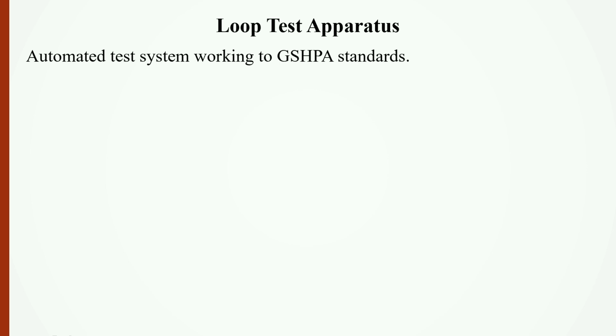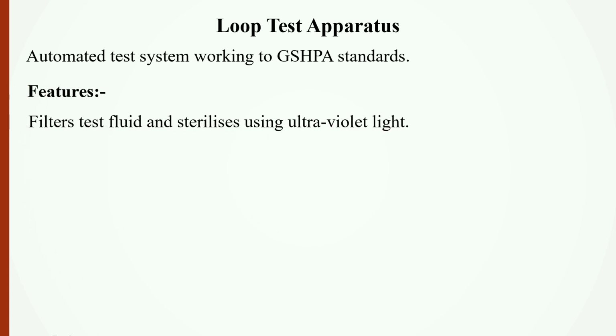So, the loop test apparatus. What I've been working on is an automated system which works to that standard. The features of it are, well, we say we use potable water. If water's available on site, use it directly. If the water's been standing around for a while, it may have some contamination. So the first thing we do is we filter that water and we hit it with UV light to sterilize it.